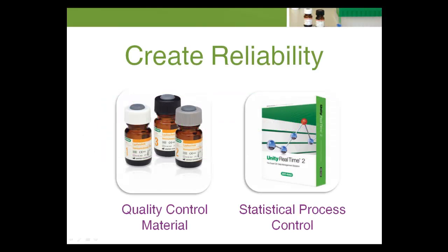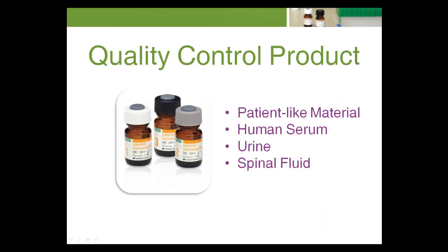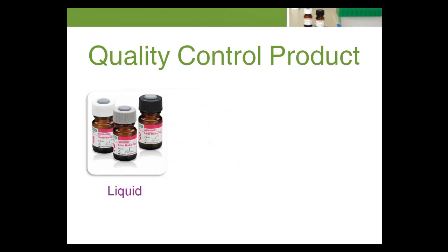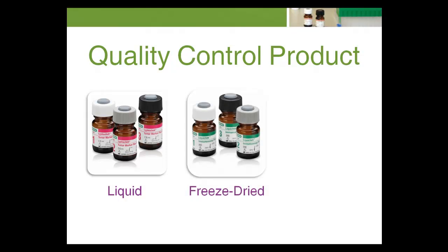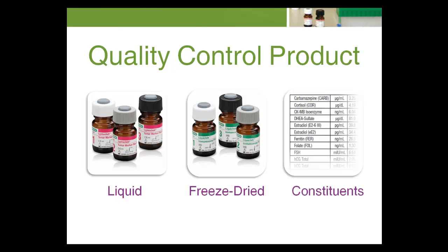The question of reliability for most testing can be resolved by regular use of quality control materials and statistical process control. A quality control product is a patient-like material, ideally made from human serum, urine, or spinal fluid. A control product can be a liquid or freeze-dried (lyophilized) material, and is composed of one or more constituents — analytes of known concentration.